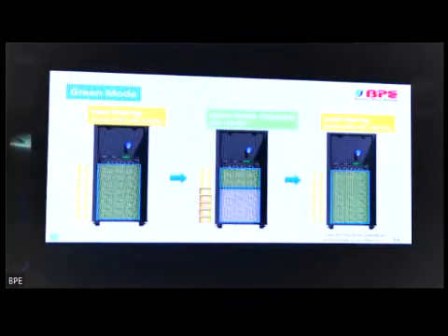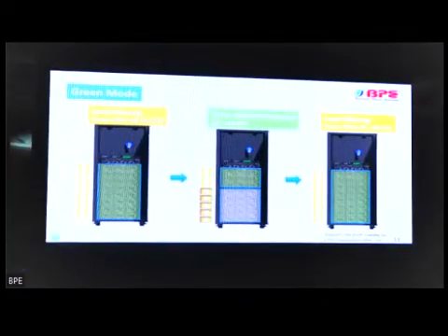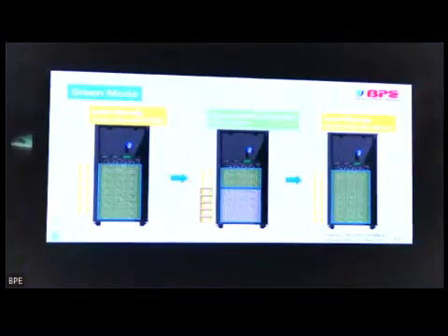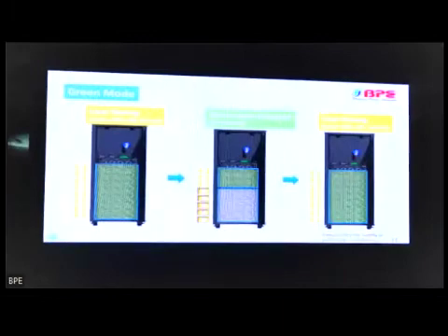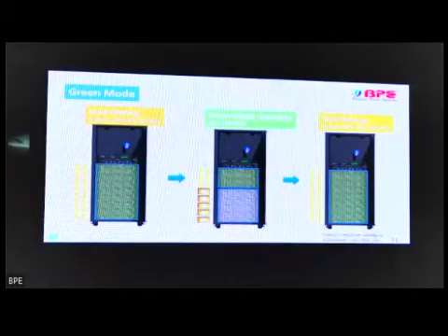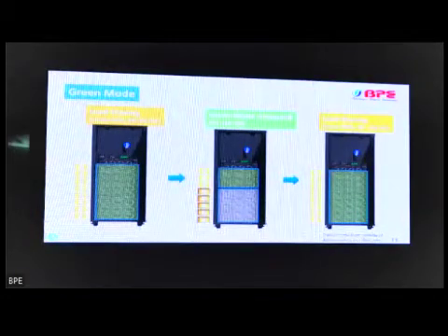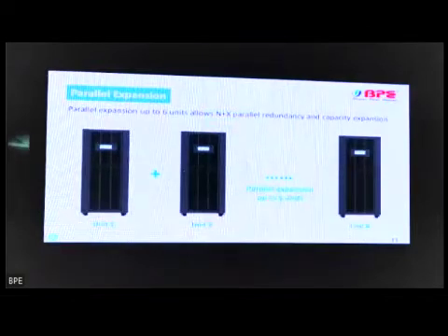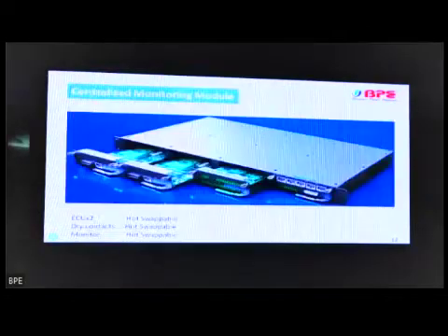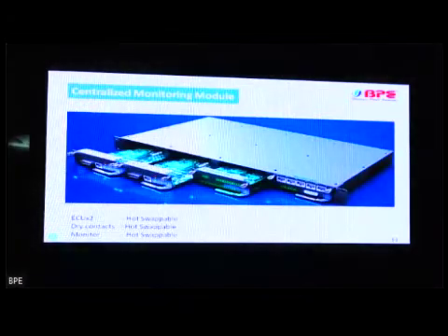There is a comparison. This is the green mode. Green mode is very useful for data center applications. Suppose your initial load is less, but you have more power modules. You can enable the green mode from the LCD itself. It will allow some of the modules to go into sleep mode so that the other modules can take more load and work in the higher efficiency area. So it will increase your online efficiency. And once your load increases, the other modules will automatically come into the picture.